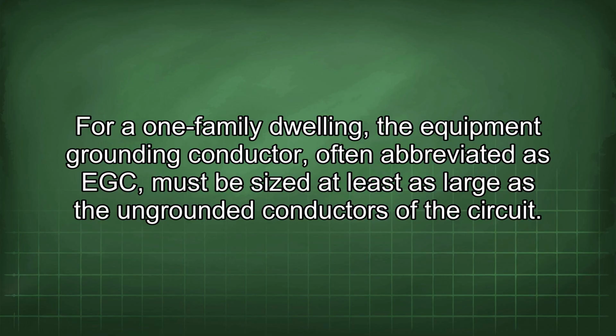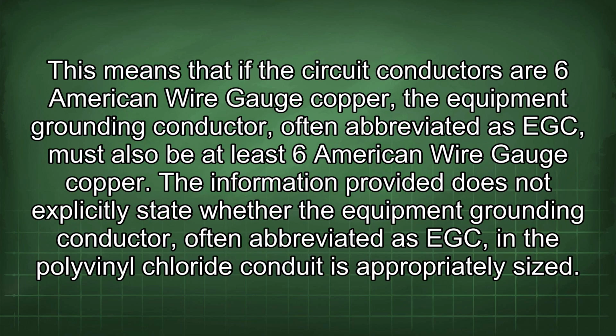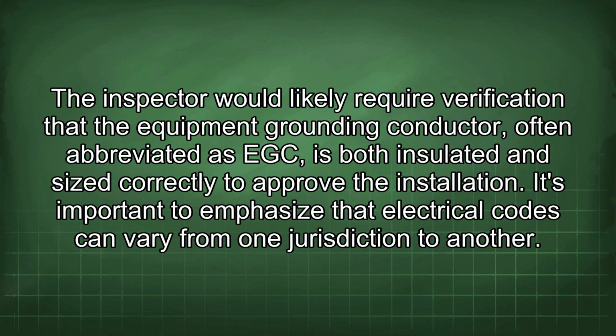For a one-family dwelling, the equipment grounding conductor must be sized at least as large as the ungrounded conductors of the circuit. This means that if the circuit conductors are 6 American wire gauge copper, the equipment grounding conductor must also be at least 6 American wire gauge copper. The information provided does not explicitly state whether the equipment grounding conductor in the polyvinyl chloride conduit is appropriately sized. The inspector would likely require verification that it is both insulated and sized correctly to approve the installation.